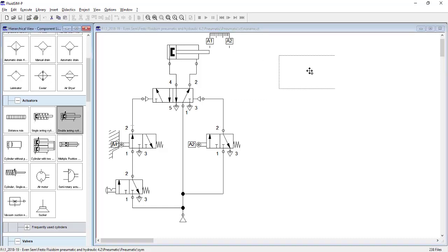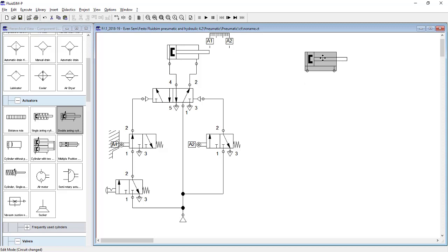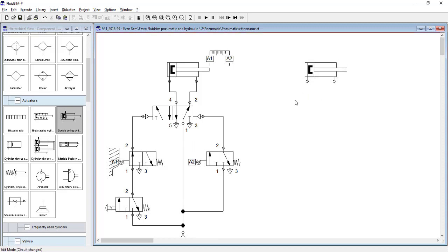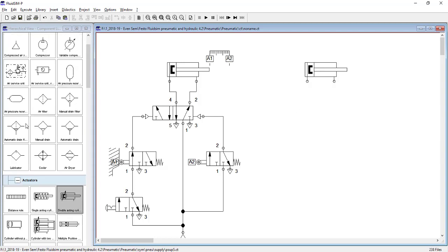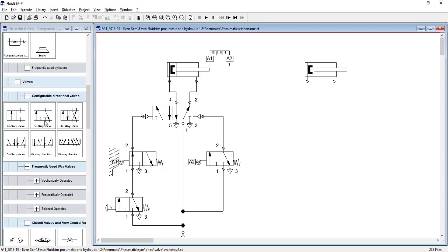See, the pneumatic part is very simple and will always remain the same for most conditions. First of all, what do you have to do? You have to do A plus A minus motion. To do A plus A minus motion in electropneumatic, there is only one alphabet, A. So you will require only one double acting cylinder. Now to control this double acting cylinder, what will you require? You will require a 5/2 direction control valve, right? Whenever you have a double acting pneumatic cylinder, you require a 5/2 direction control valve.